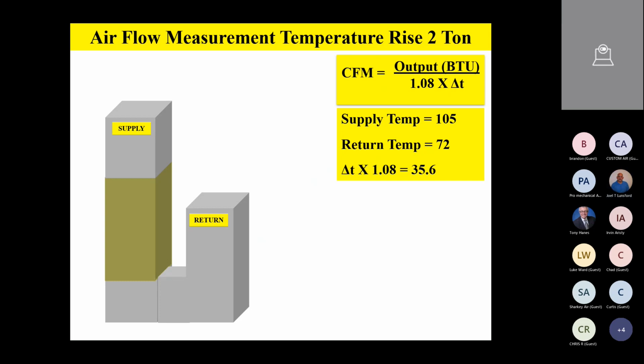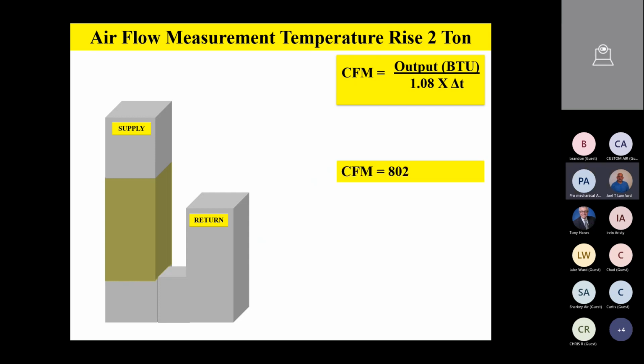35.6. Now, to complete this formula, fellows, you're going to divide the output by that 35.6. So our output, remember, was 28,563 divided by 35.6. And that gives us a CFM in this example of 802. So this is what we call the temperature rise method, fellas. This works very, very well. This is kind of an old-timey way of doing it.